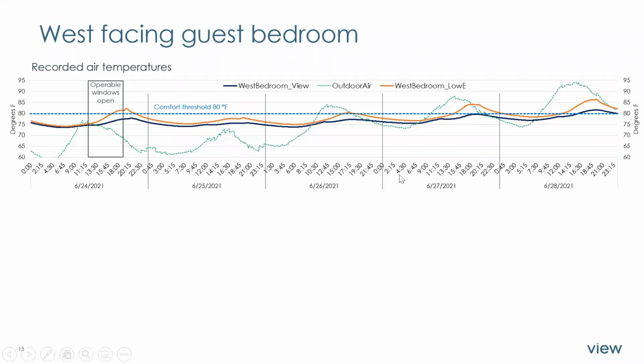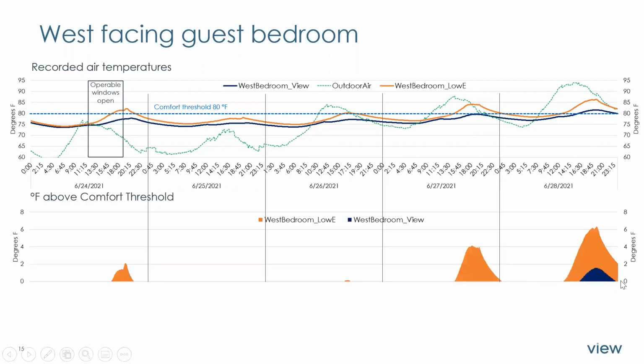If we zoom in on these values, since it's a bit harder to understand in the full graphs, I extracted the temperatures above 80 degrees. Now you can see there's a significant delta, about 4 to 6 degrees, on the hottest day, between the EC view smart glass and the low-E window.